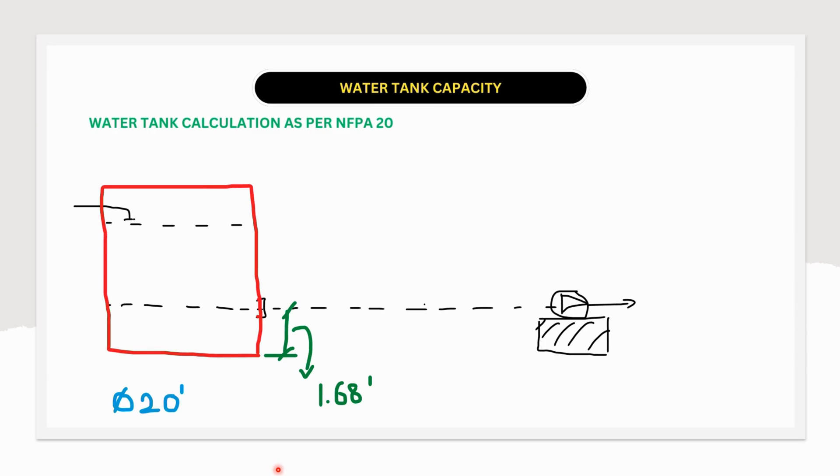Let us try to calculate the water tank capacity as per NFPA 20 requirements. For example, our system demand is 1000 GPM for 30 minute duration. Then the capacity would be 30,000 gallons. But based on these 30,000 gallons, we cannot decide the water tank size because there are few things to be considered before we select the water tank size. I will explain you in detail.